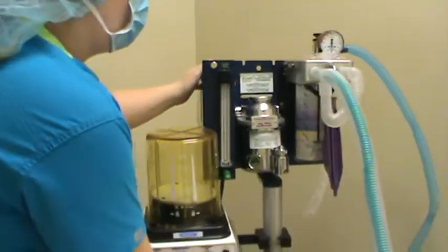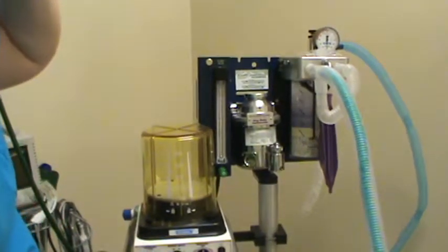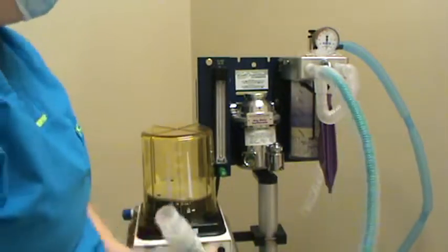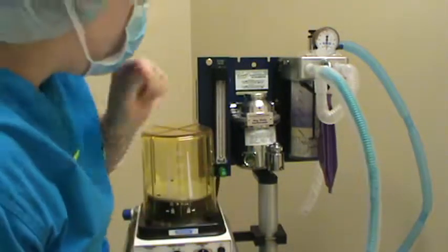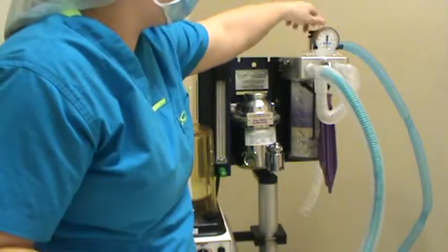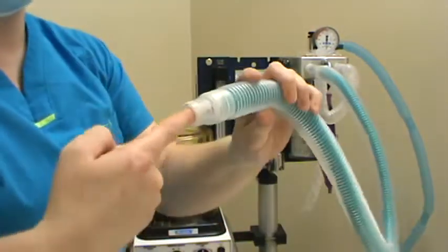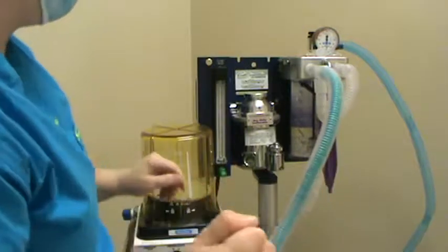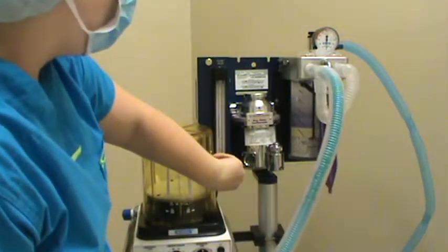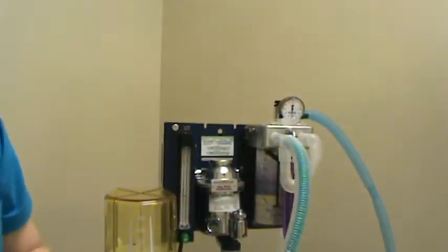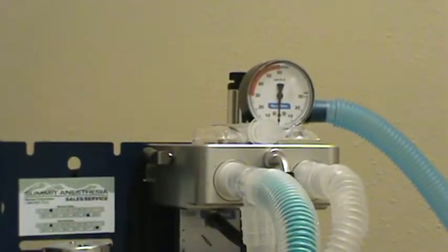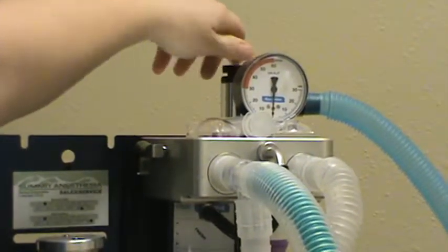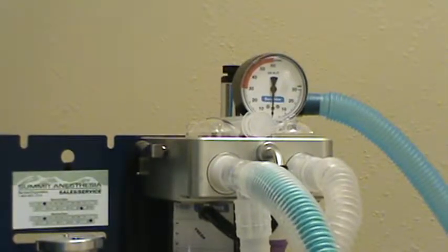The last thing we're going to do is perform a low pressure test to be sure that the machine can hold pressure and that there's no leaks anywhere in our system. We're going to close the pop-off valve, occlude the tube with our finger, turn on the oxygen, and fill our bag to about 30 centimeters of water and see if it holds.